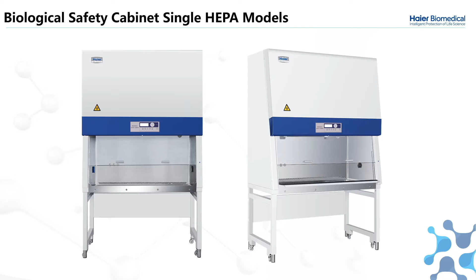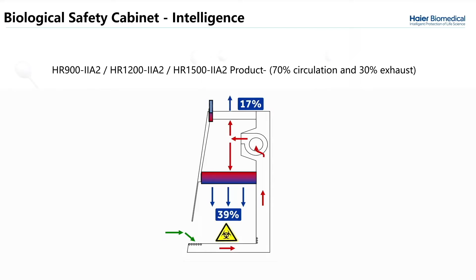So I'm just going to go through a few key products available on the single HEPA range. So the single HEPA intelligence range is available in 900, 1200 and 1500 working width. These are IIA2 models, which means they're 70% recirculating and 30% exhaust. They use our intelligent constant air velocity system. They feature an ultra-efficient ULPA downflow and an ultra-efficient HEPA outflow filter.